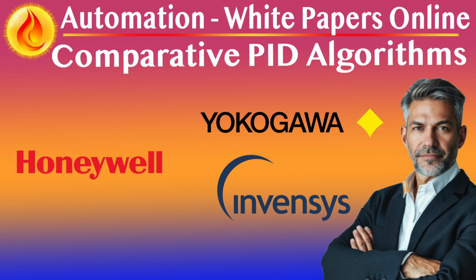In constraint-prone operations, e.g. refining utilities, Invensys offers tighter integration of overrides, ramping, and APC. In high-noise or high-frequency environments, Yokogawa's derivative control and PV filtering offer more tunable noise suppression. For plant-wide loop performance optimization, both offer excellent tuning tools, but Invensys tools are more operator-accessible, while Yokogawa tools are model-centric. Conclusion: Yokogawa and Invensys deliver powerful PID control capabilities, but with distinct design philosophies.